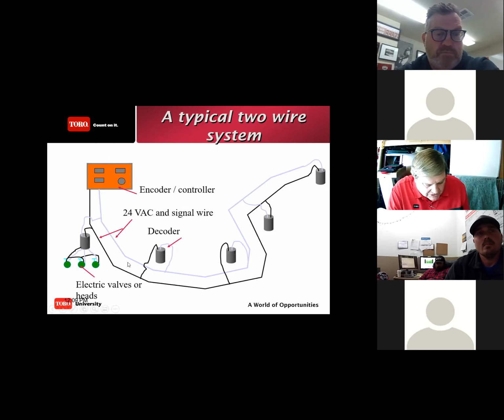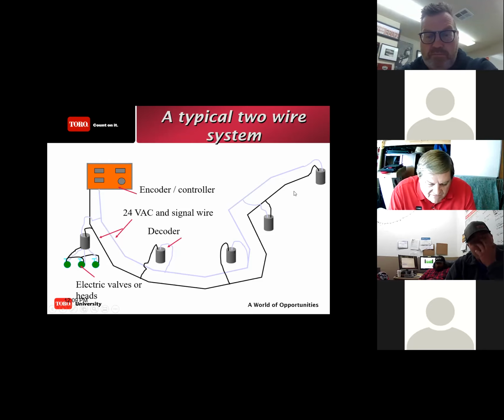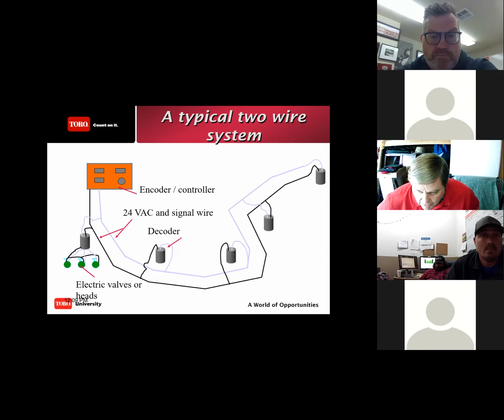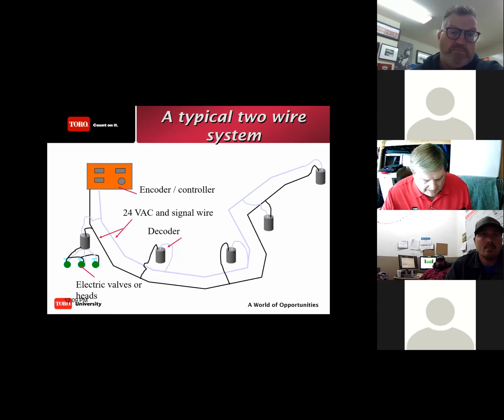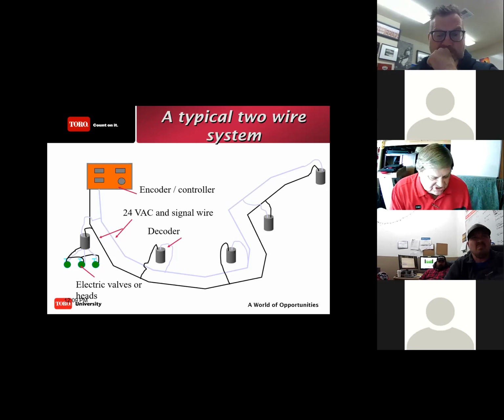Next, I want to call your attention, not to the polarity or the decoder, but to the very end of the line. Your 2-wire path doesn't just arbitrarily end. It must conclude at a decoder being used for anything: a valve, a moisture sensor, a weather sensor. You just can't have the wire end. And there are some unique issues about that as we get further along. But I needed you to see from a 30,000-foot view what the 2-wire system is.